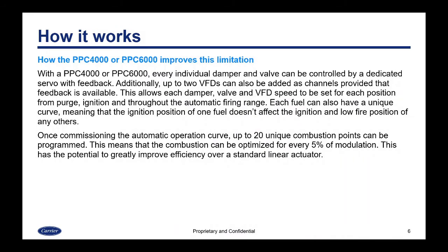So how does the PPC4000 or 6000 improve this? With the PPC4000 or PPC6000, every individual damper and valve can be controlled by a dedicated servo with feedback. Additionally, up to 2 VFDs can also be added as channels, provided that feedback is available from the VFDs. This allows each damper, valve, and VFD speed to be set for each position, from purge, ignition, and throughout the automatic firing range. Each fuel can also have a unique curve, meaning that the ignition position of one fuel doesn't affect the ignition and low fire position of any of the others.